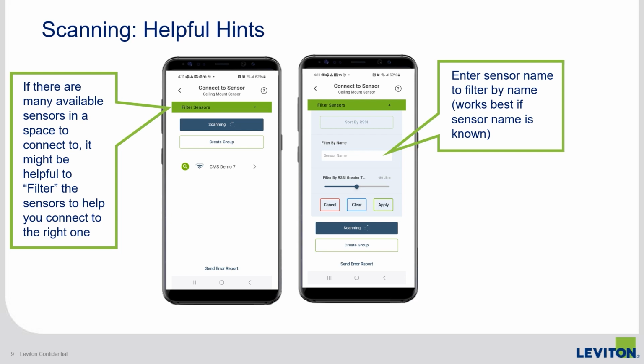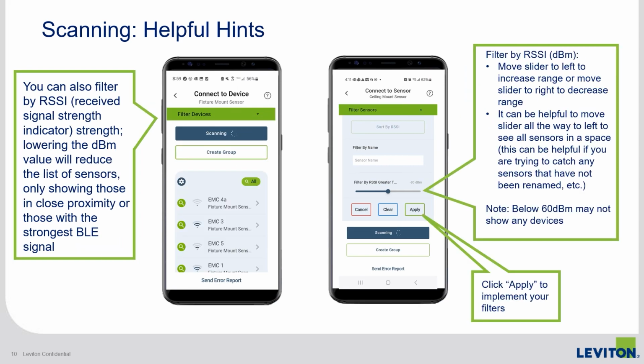Depending on the size of the space and number of sensors, you may see a large number of sensors appear on the scan list. If you'd like to filter the results, you have a couple of options. First, you can filter by name. This is useful only if you already know the sensor name. The filter is typically used after you've connected to and renamed a sensor. Another filter option is to adjust the RSSI strength. Default is -80 dBm, so anything less than -80 will reduce the strength and distance so that only sensors closest to you will appear. Another option is to increase the RSSI strength. This is helpful if you are looking for any sensors not appearing on the original list and may be further away.